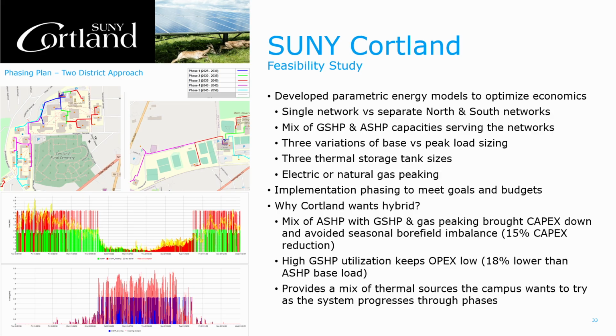So why Cortland wants a hybrid solution: it really showed that a mix of air source and ground source helped with borefield imbalance, taking some of that load off the borefield by using air source, but it also helped reduce the initial capex of the equipment by over 15% compared with going with just ground source heat pumps. But at the same time, utilizing ground source keeps the OpEx low, so it's a balance of that CapEx and OpEx, trying to find what that optimization is.